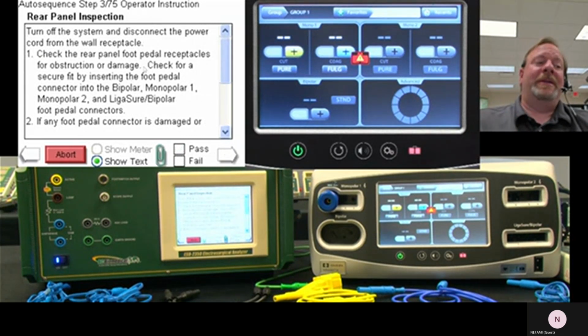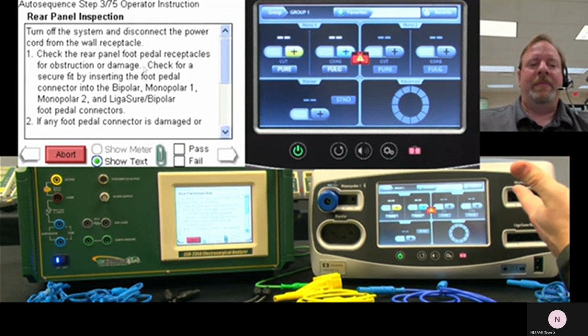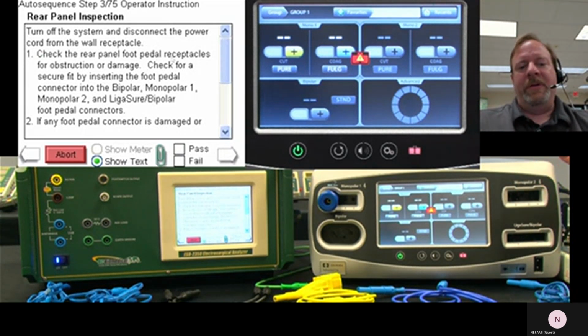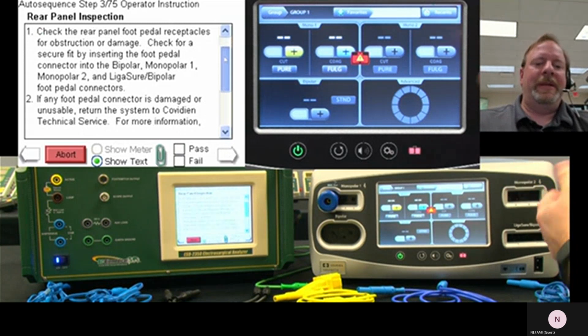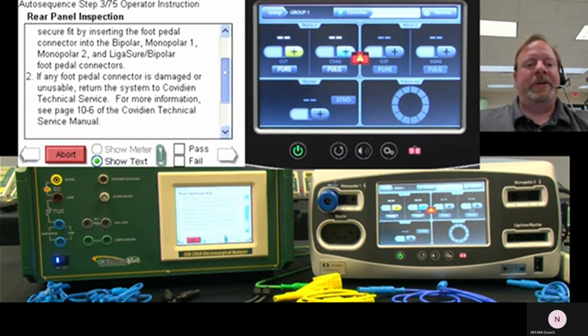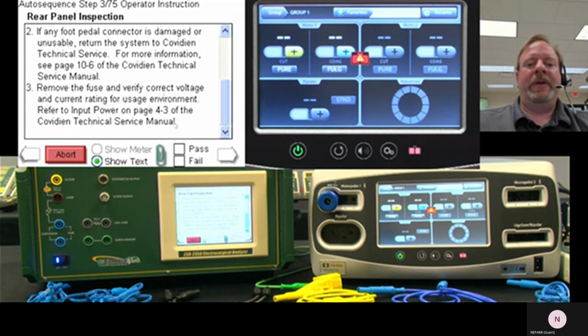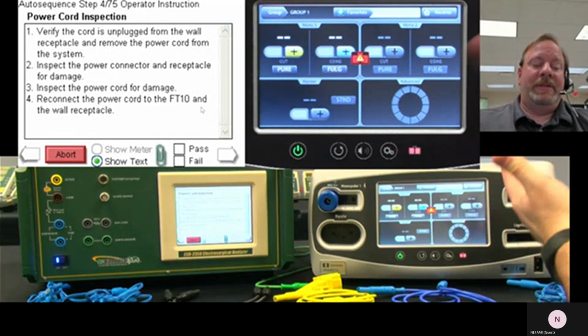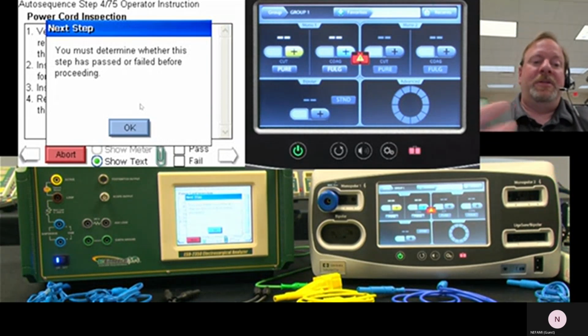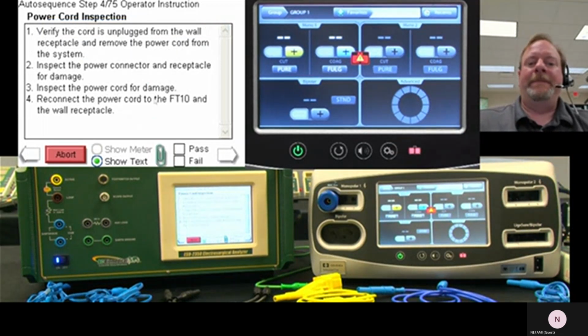Okay, so rear panel inspection. Now we're getting into the meat of the PM. So you're going to check all the foot pedal receptacles, make sure there's no broken pins, make sure all the contacts are good, all the cables are okay, that sort of thing. And again, there's really nothing for the 2350 to do other than tell you what to do and make sure you do it. Now I can try and advance through the test without doing this step, but I can't. It says it either has to pass or fail. You cannot get to the end of the test without selecting one or the other. So in this case, I did my inspection, reading my instructions carefully.